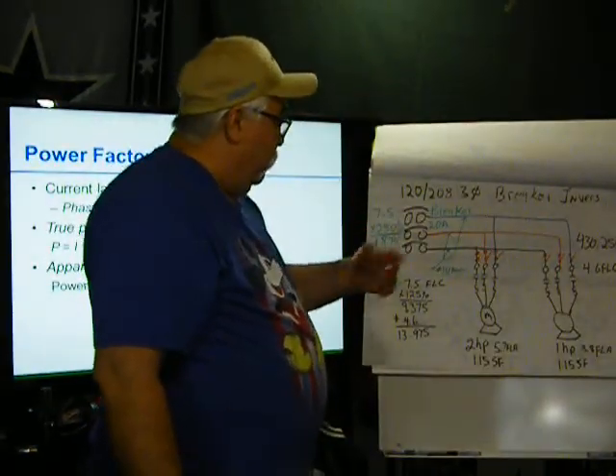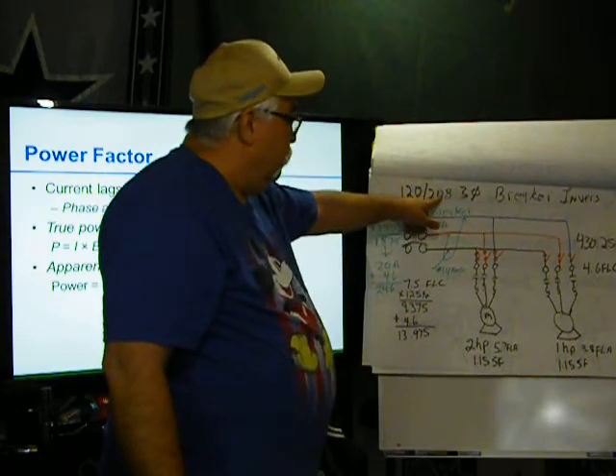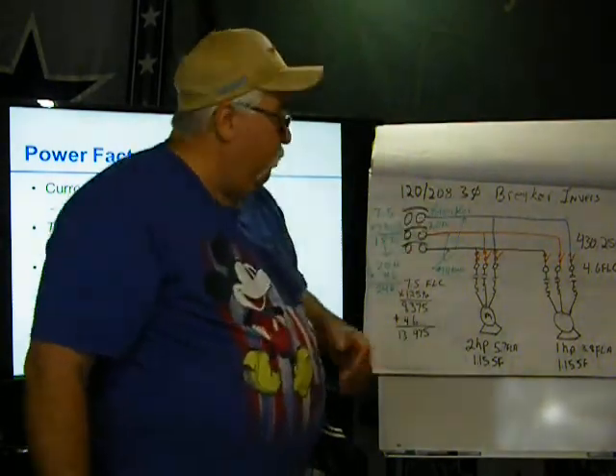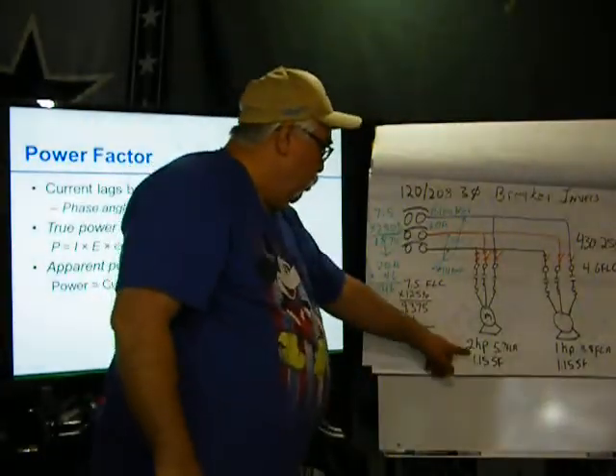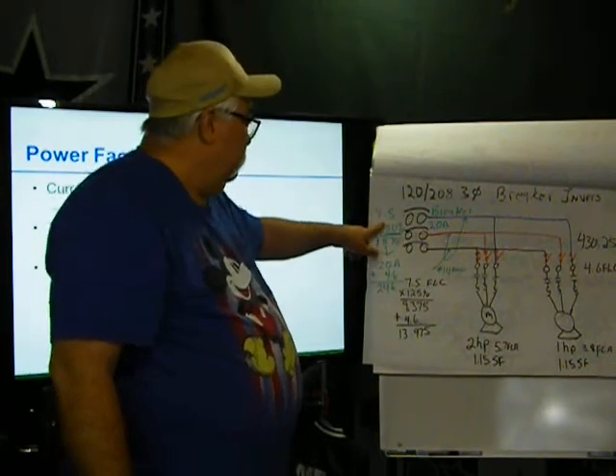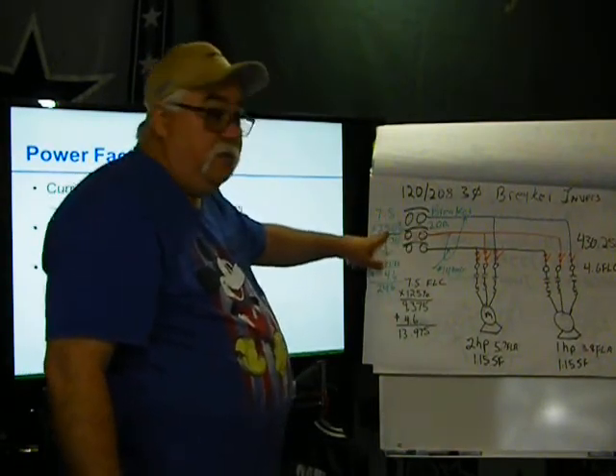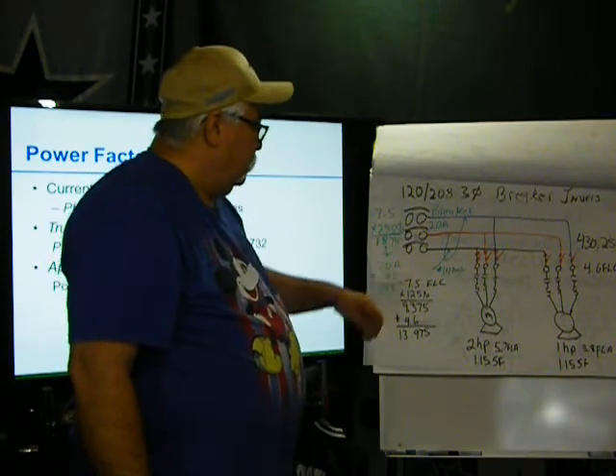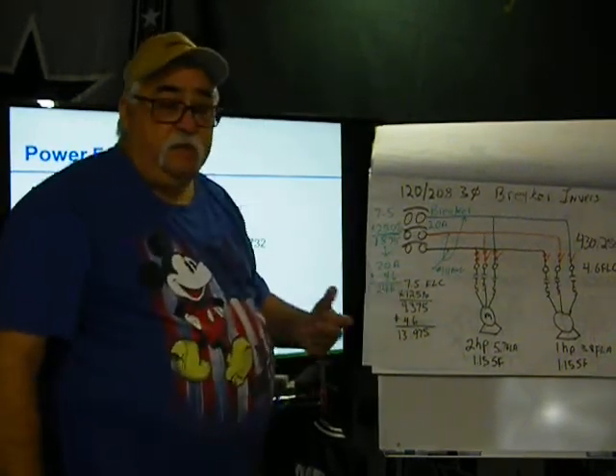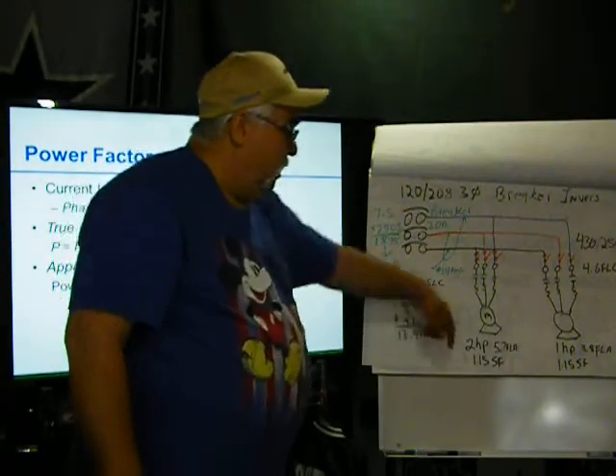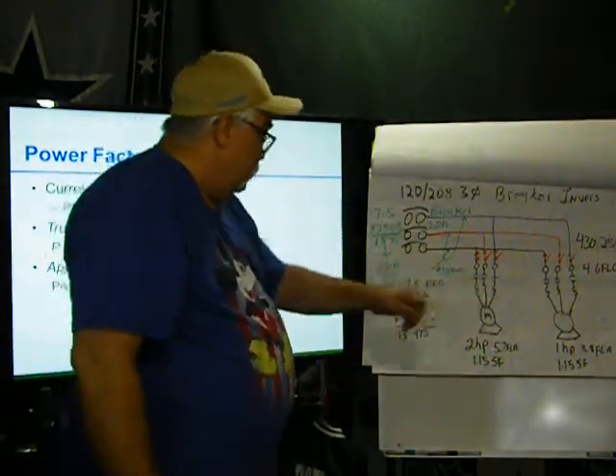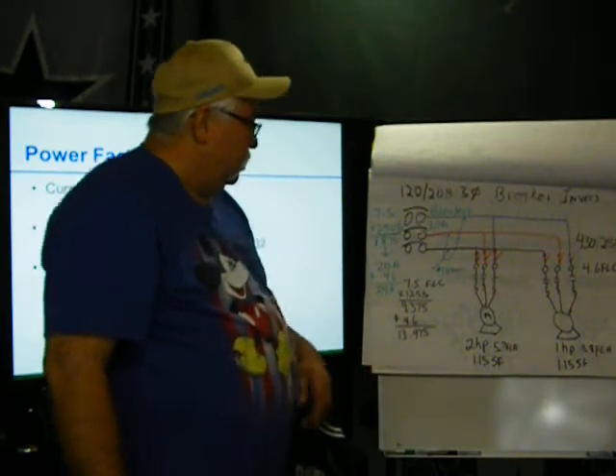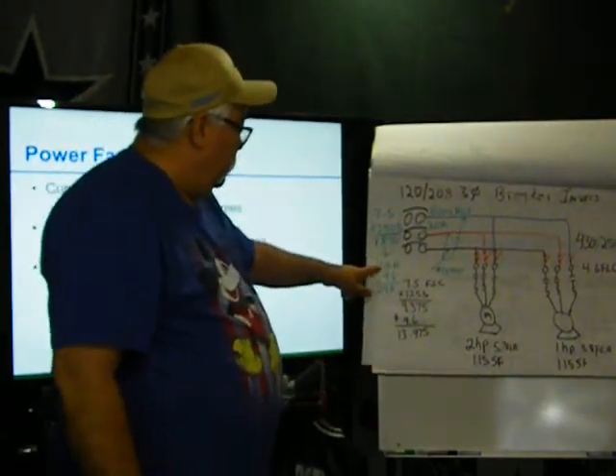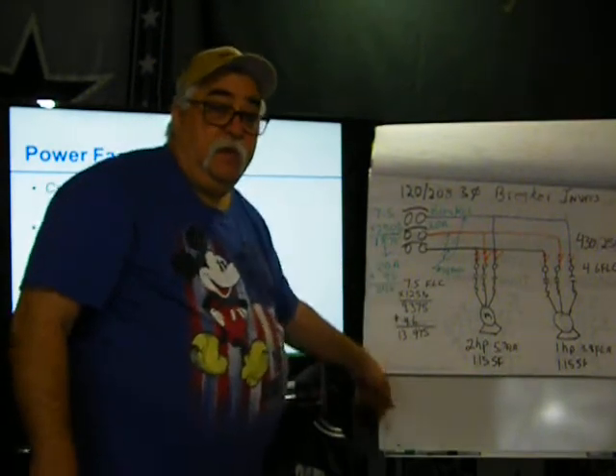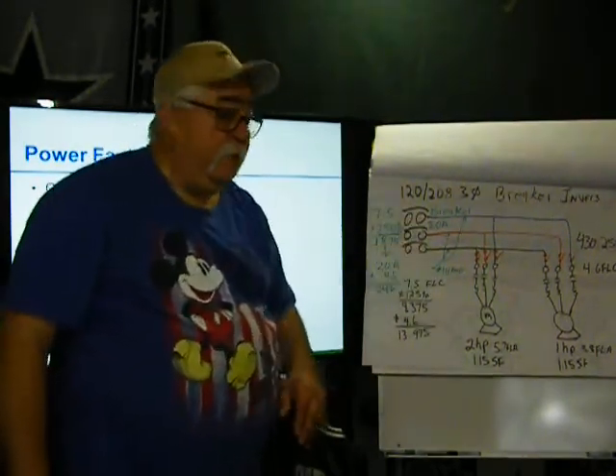So again, because this is three-phase, I'm at 208 three-phase, so I went to Table 430.250. I had it down here, 430.250. For the 2 horsepower, it was 7.5. Okay, we're using a breaker, multiplied by 250%, gives me 18.75. Next breaker size from there is a 20. So I made it a 20 and then added all other motors. I added that second motor, 4.6, so it's 24.6. Code says this, because I already went up here, I can't go up here. That means I have to go back down, so my breaker would be a 20 amp breaker.